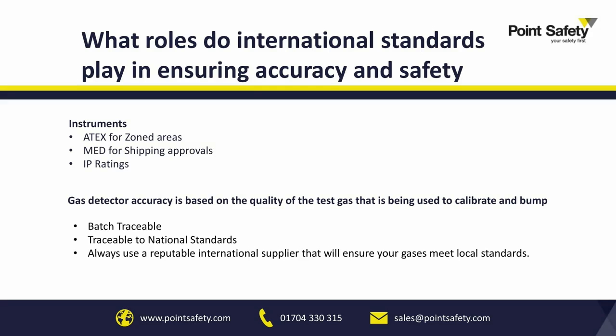When we come to the calibration, the accuracy of each calibration is not really based on the equipment. It's based on the test gas that we're using to calibrate and bump those meters. So it's vitally important that you are purchasing your test gas from a reputable supplier like Spantech, as all their test gases will be batch traceable. They'll be traceable to national standards, so it's very important we use those correct gases, that we can rely upon their concentration, and that gives us a line back to national and international standards.